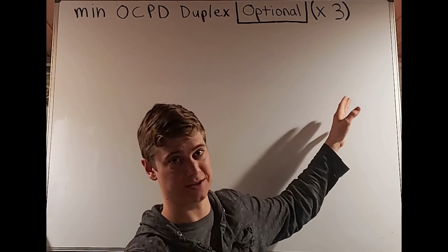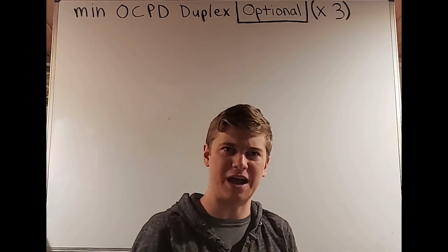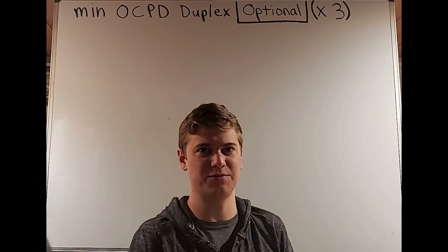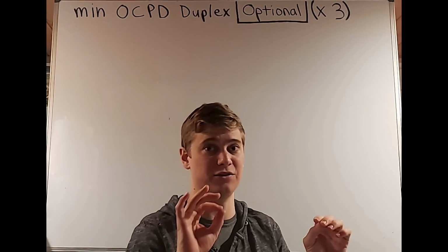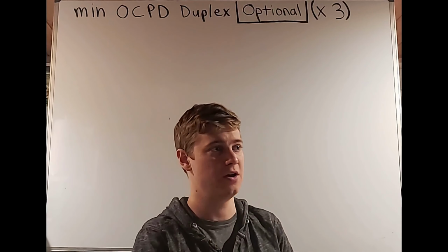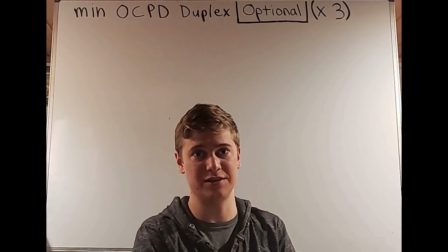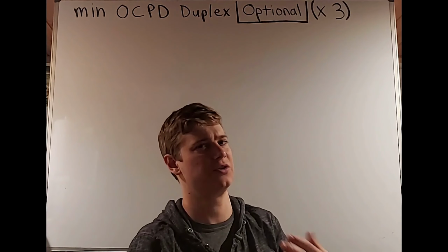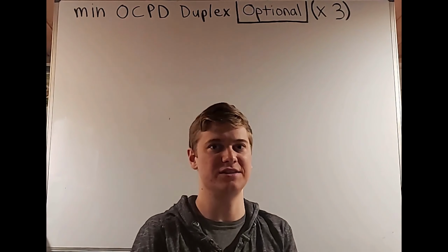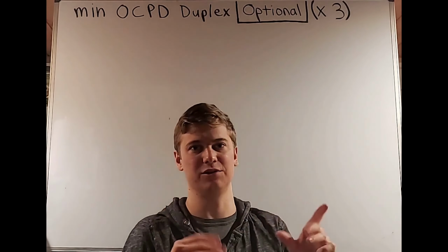The difference here is that in the optional method, it's sort of a boiled down version compared to the standard method. There's a lot less steps, there's a lot less demand factors and weird exact rules. We're basically adding everything together, and then we're doing one demand factor at the very end. It makes it a lot quicker and simpler, and I would consider it more of an estimate compared to the standard method, where you're getting a little closer to figuring out certain particular things.